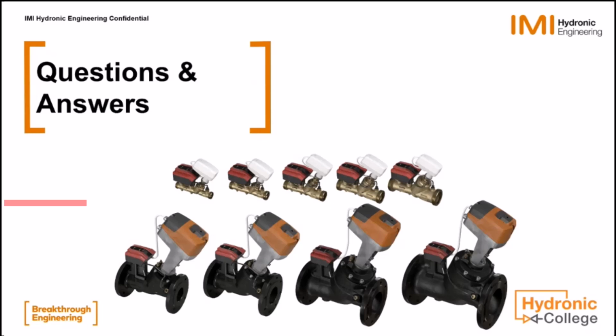Okay, anything else? I've just a thought on the setback, where we can define what happens over each of the 7 days. Will there be a register entry in the bus that will say enable setback regime or disable setback regime? I'm just wondering, if we're looking at setting back the heating when we're coming into winter, in October we would want to run setback, in November we'd want to run setback, and December, January, February you might not want to run your setback. But obviously that then becomes super complicated in terms of the TA Smart. Is there a register entry that says turn it on or turn it off effectively?